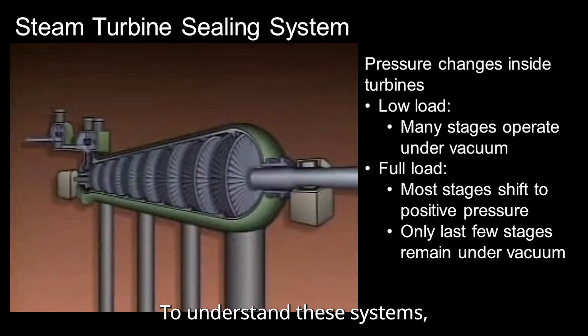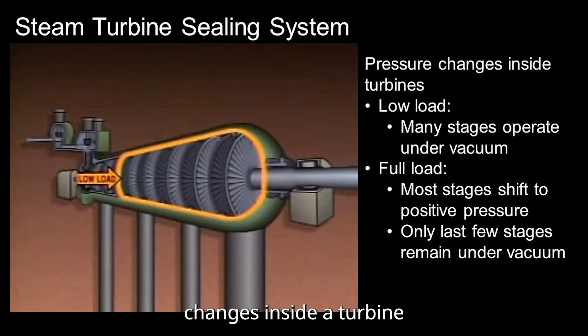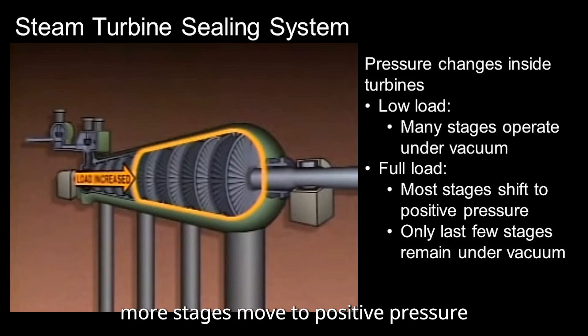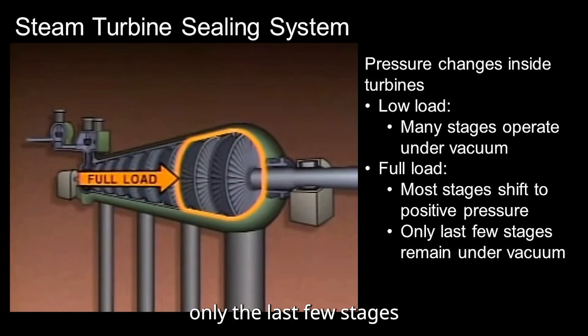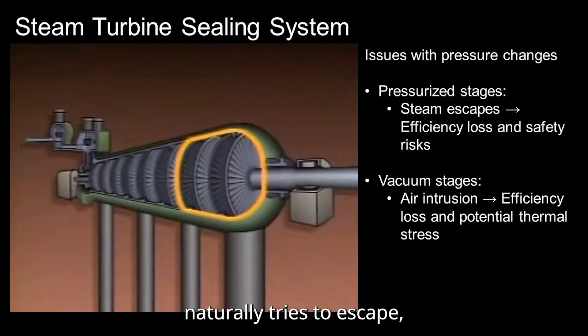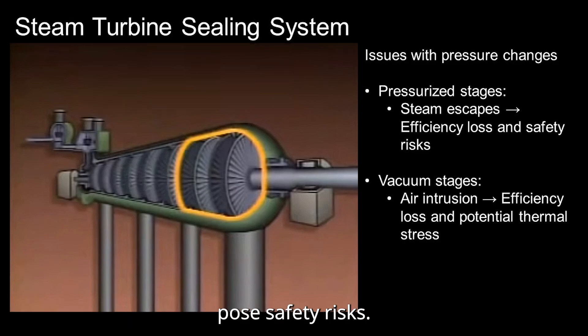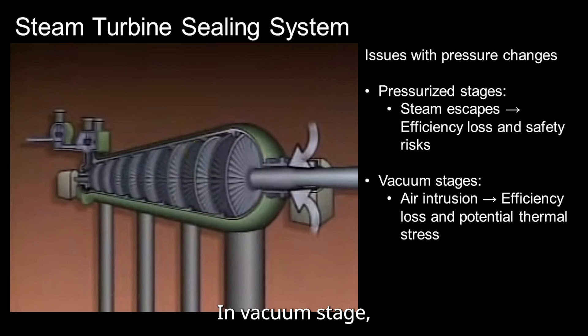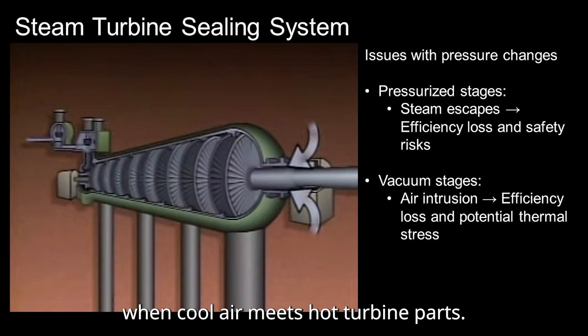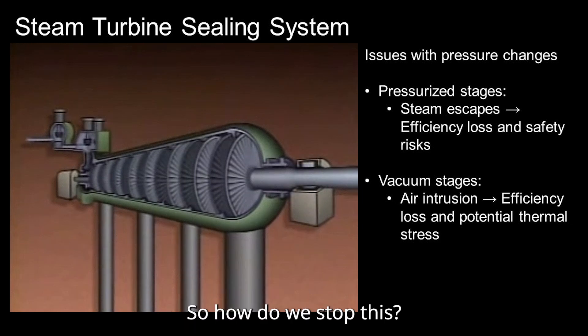To understand these systems, it helps to know how pressure changes inside a turbine. At low loads, many turbine stages operate under a vacuum. But as load increases, more stages move to positive pressure. At full load, only the last few stages are still under vacuum. In pressurized stages, steam naturally tries to escape, especially where the shaft penetrates the casing. Without controls, steam loss would lower efficiency and pose safety risks. In vacuum stages, air tries to sneak in, reducing efficiency because air removal is energy intensive. It can also cause thermal stress when cool air meets hot turbine parts.